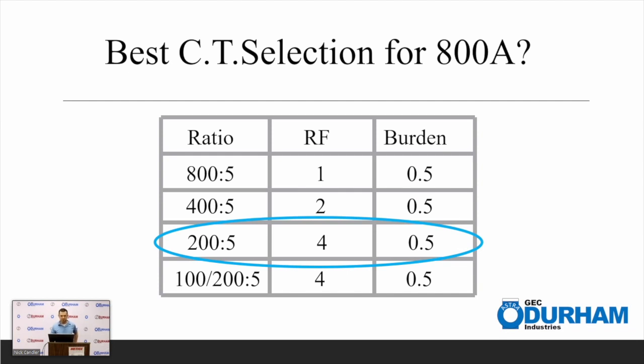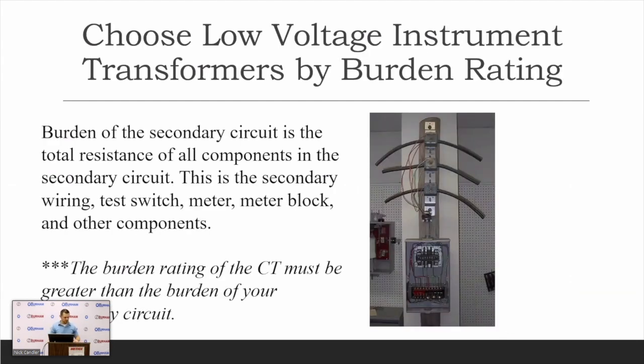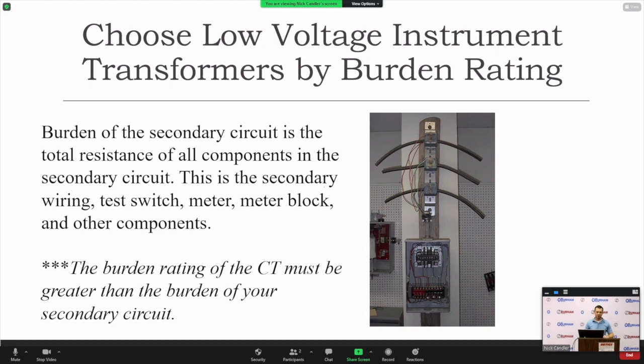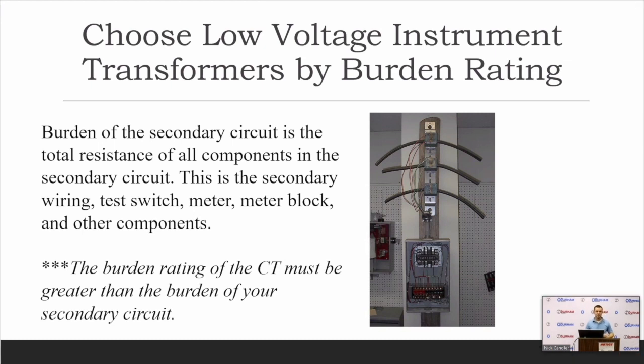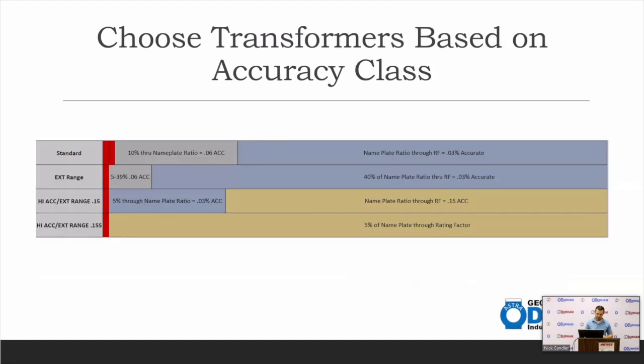We'll get into burden here in just a few minutes. For now, the burden of the secondary circuit is the total resistance of all the components in the secondary circuit. This is the wires, the test switch, the resistance or burden in the meter block, and any other components that are part of that secondary circuit. The burden rating of the CT must be greater than the burden of your secondary circuit. That's important, because if it isn't, it drives the test point outside of that ideal accuracy class. It also reduces secondary current to the meter. Yes, good point. So again, we want to choose the transformers based on accuracy class.